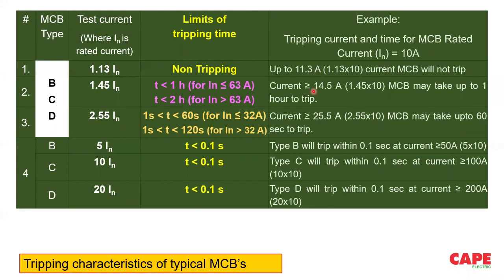There are 3 types of MCBs available: Type B, Type C, Type D MCB. I have put the tripping characteristics of the MCBs. Each of these MCBs has its typical way of disconnection, especially when it comes to instantaneous tripping. A Type B MCB, 3 to 5 times the nominal current. Type C, 5 to 10 times current. Type D, 10 to 20 times current. So basically, these 3 types of MCBs must be selected appropriate for a certain location.